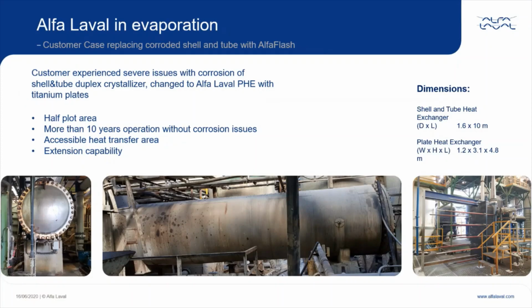The process designer and system integrator originally selected shell and tube technology for this position, since they were skeptical of using plate and frame technology, afraid that the crystals would plug the channels. In order to still be affordable, this large piece of equipment was manufactured in duplex stainless steel. However, after only 3 months of operation, the corrosion issues were severe, and it was clear that a higher grade material had to be used. But building this shell and tube unit with a titanium tube bundle would be extremely expensive and delivery time would be very long.